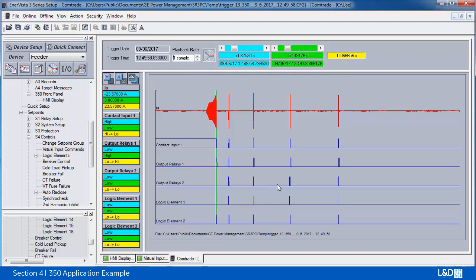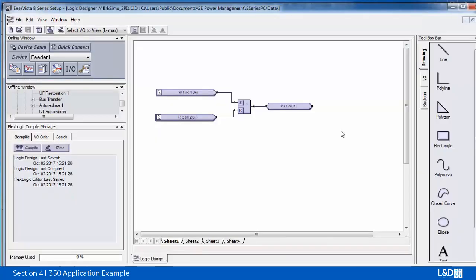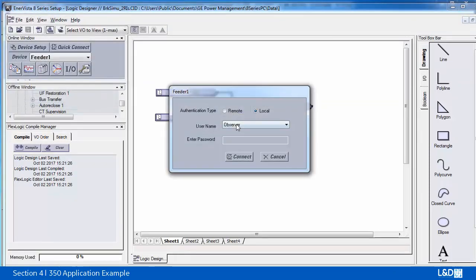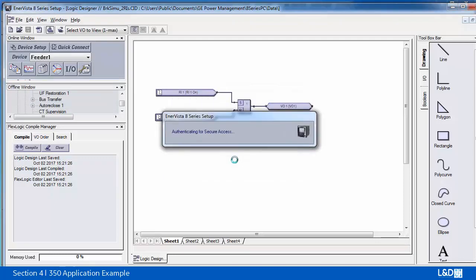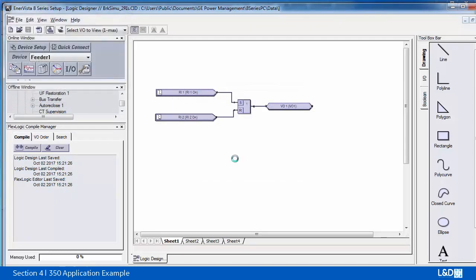Relay 2 is the close. The 4 shots of the reclose, the time is the dead time settings. Each time is a little longer. Then because we enabled the logic elements, we're using logic element 1 and 2, which are also assigned to the trip and the close. So logic element 1 is associated with the manual or auto close, and element 2 is for the trip. From the 8 series side, we should see the remote input from the logic element of the 350.